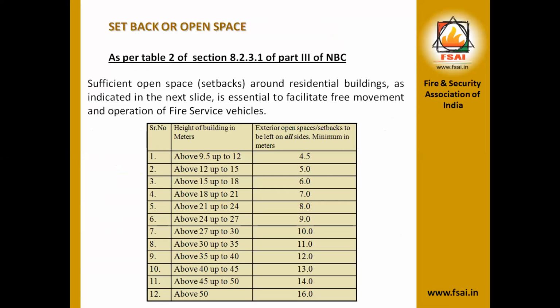Setback or open spaces. There should be sufficient open spaces around residential buildings, as indicated in the next slide table. These are essential facilities for the movement and operation of fire service vehicles. If the height of the building is 9.5 meter to 12 meter, the setback distance should be 4.5 meter. Likewise, for 12 meter to 15 meter, it is 5 meter. For 15 meter to 18 meter, it is 6 meter. So for every rise of 3 meter in the height of the building, the setback distance increases by 1 meter. At the end, for the height of 50 meter, the setback distance should be 16 meter.